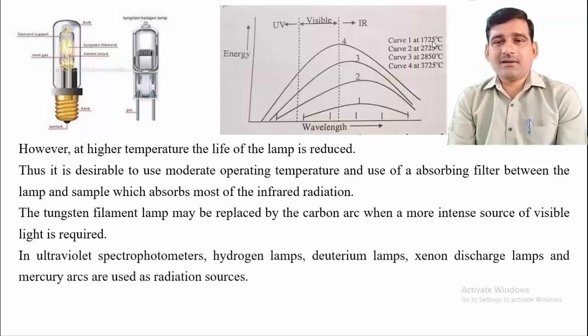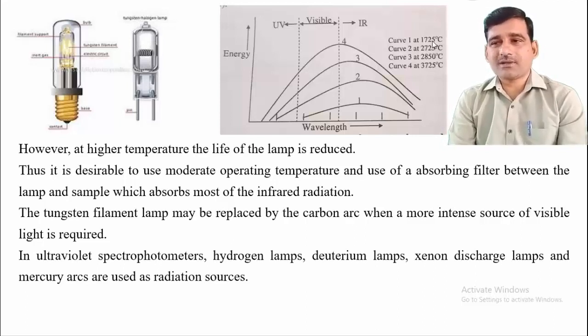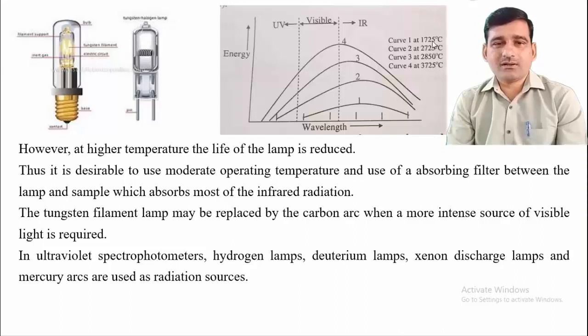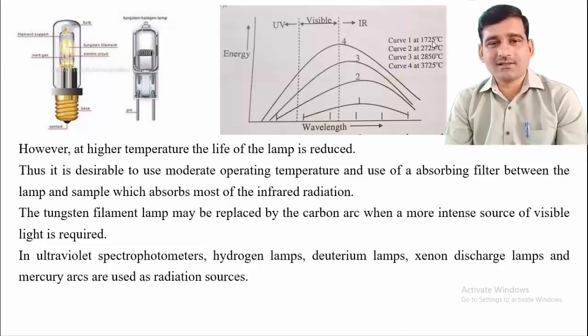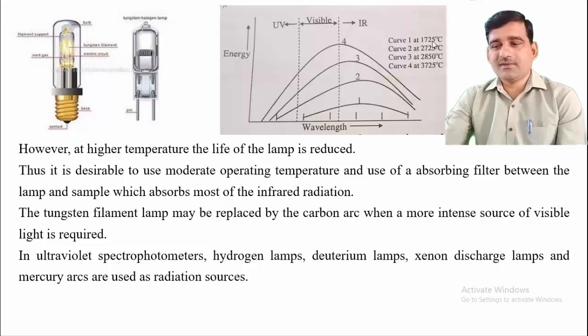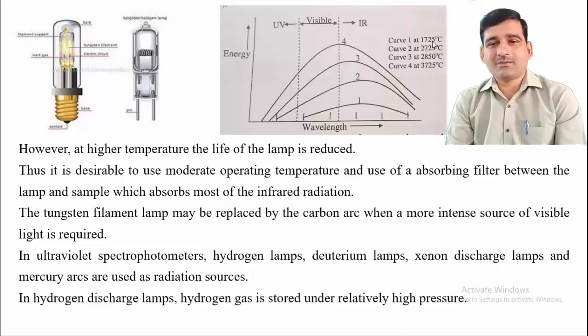In ultraviolet spectrophotometry, hydrogen lamp, deuterium lamp, xenon discharge lamp, or mercury arc lamps are used as radiation sources. This is because tungsten filament and carbon arc lamps provide light only in the visible and near-IR region. If radiation in the ultraviolet region is required, we use hydrogen, deuterium, xenon discharge, or mercury arc lamps.